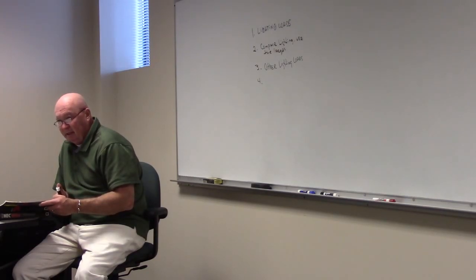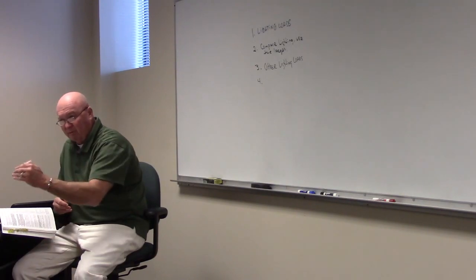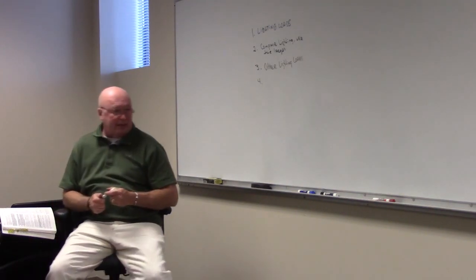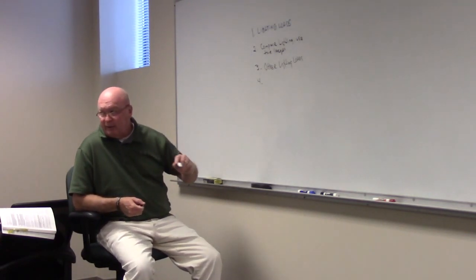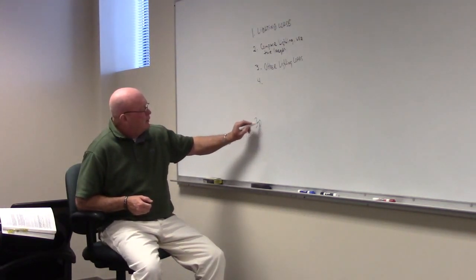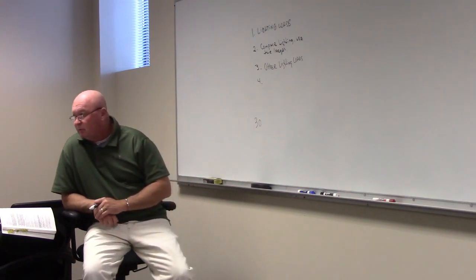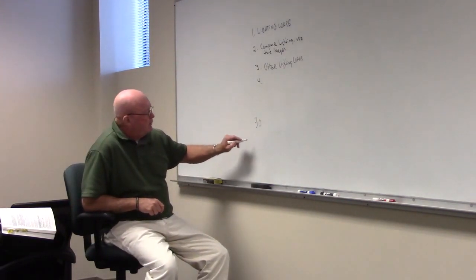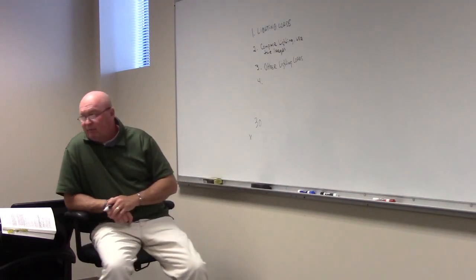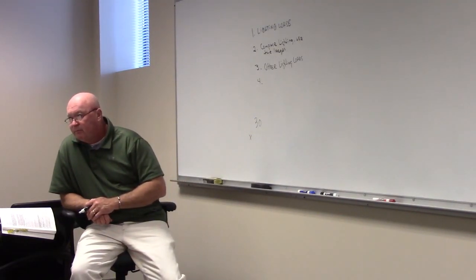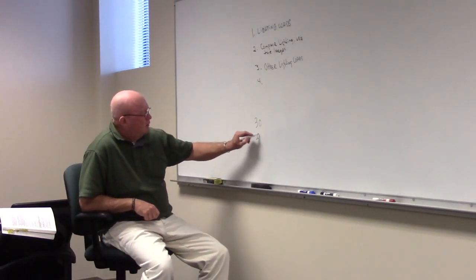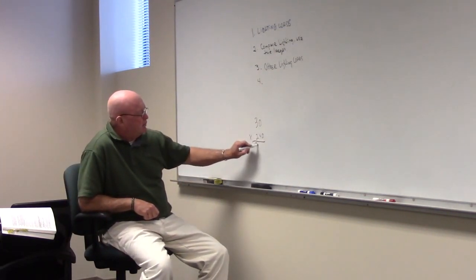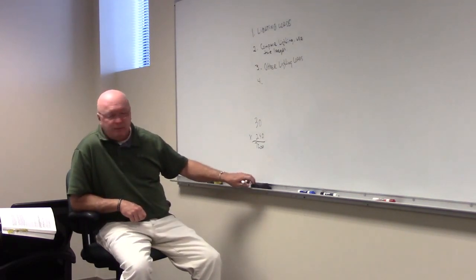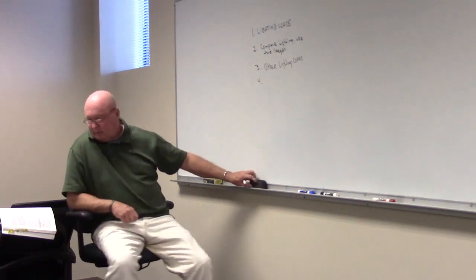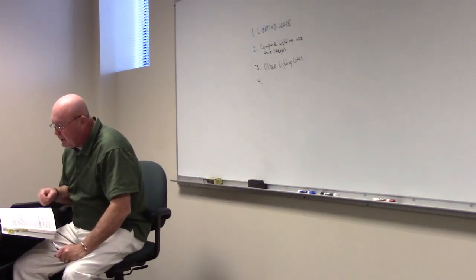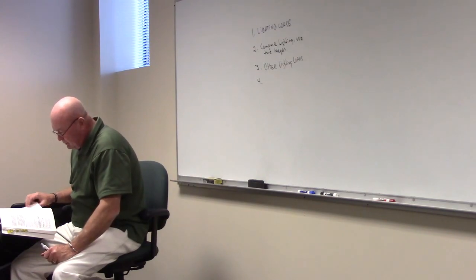So we're just going to go by, in other words, if we've got something specific, something special, we're going to find what that is. For example, to get the volt amps, let's say we have a 30 amp, 240 volt plug. How are we going to figure out how many volt amps it is? 30 times 240. Yeah. And we don't need to do it, but it's like 7,200. Okay, that's how we get to that. That's just a specific thing. All right. We look at the other part, H, mixed multi-outlet assemblies.